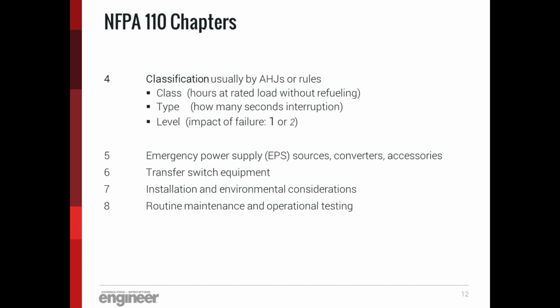After the 2010 edition was published, when we published the 2013 edition, that requirement was actually removed and moved to the annex. However, because the 2010 edition of 110 is the one that's invoked by the 2012 standards, it still invokes the 96-hour requirement in certain seismic zones.